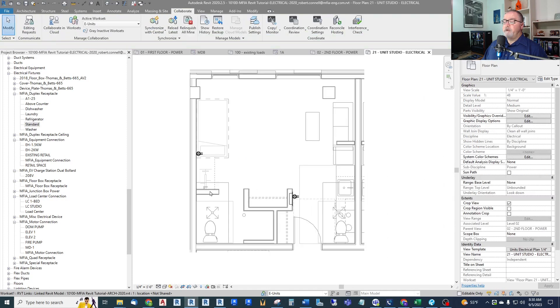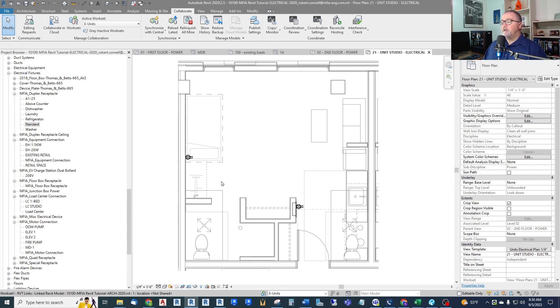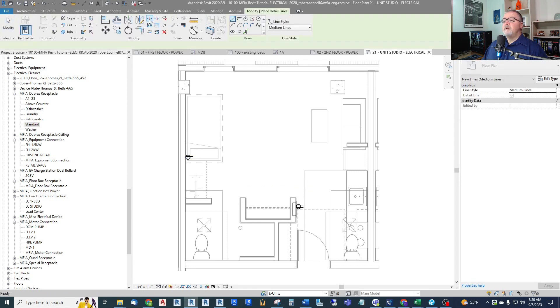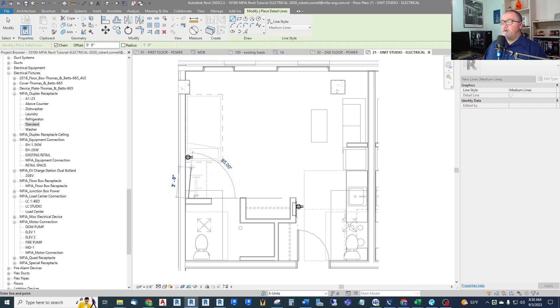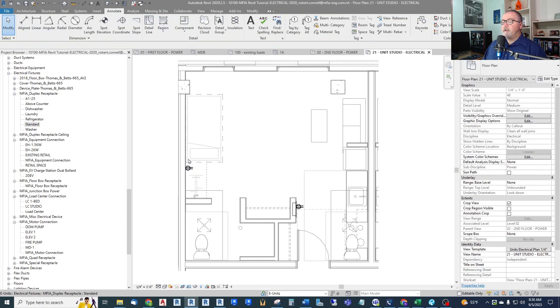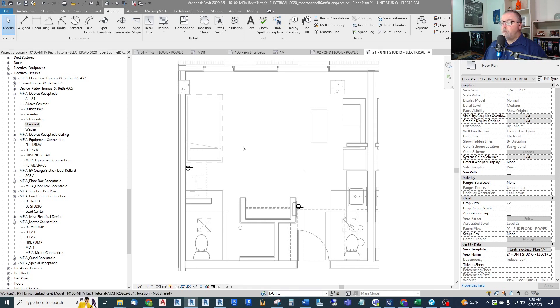Following my NEC rules, which is a whole design issue there, not just a drafting or modeling issue, and put my receptacles where they need to go. A lot of times just for that I will use detail lines to see dimensions. That's about three feet, it means I can go roughly another three feet. So I need to put one down there and example. And I'll go 12 feet from here and continue my receptacles. I'll put in all of my kitchen receptacles, appliances, fans, all of that in here in my Units workset.